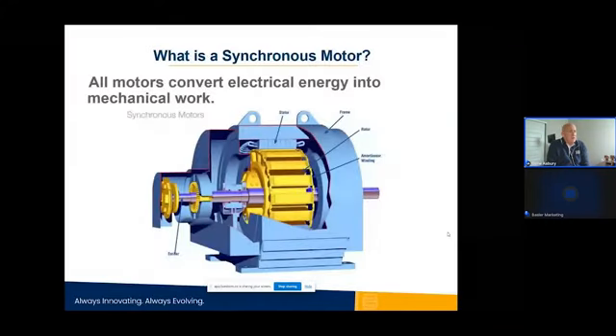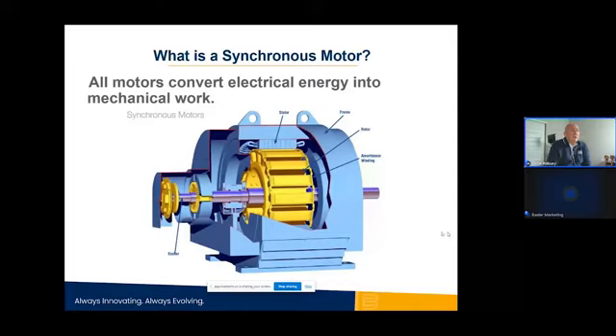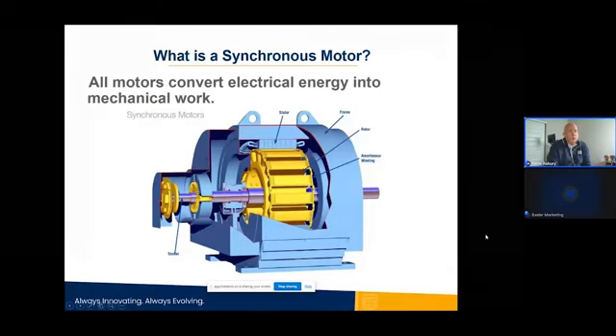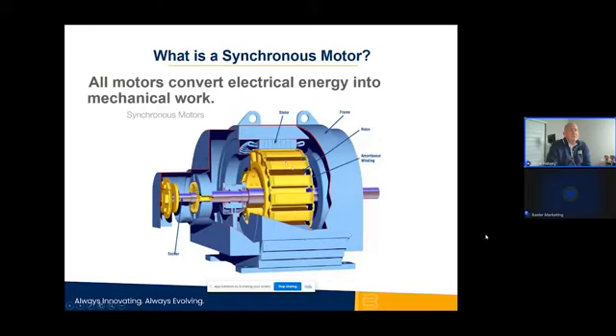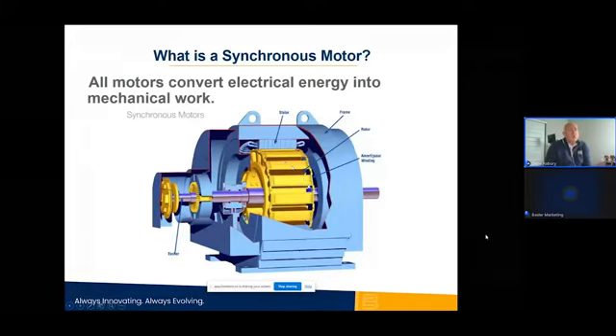This is a cutout view of a synchronous motor. You've got your different parts of it. You've got your rotor and your rotor windings, your different poles. You've got your stator windings. And then you've got your amortisseur winding, also known as a squirrel cage or a damper winding.